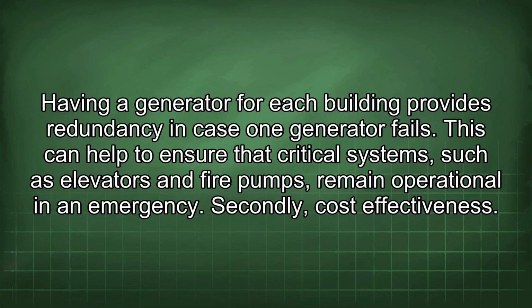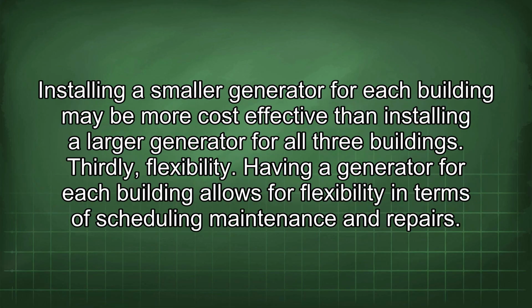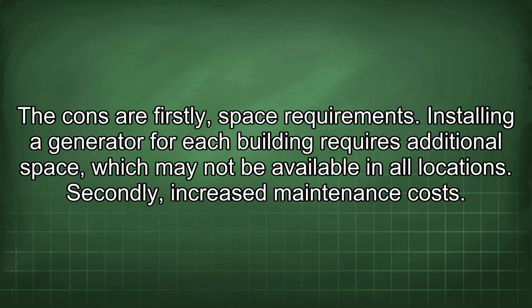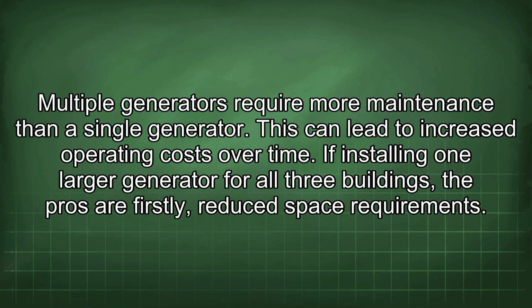Secondly, cost effectiveness. Installing a smaller generator for each building may be more cost effective than installing a larger generator for all 3 buildings. Thirdly, flexibility. Having a generator for each building allows for flexibility in terms of scheduling maintenance and repairs. The cons are, firstly, space requirements. Installing a generator for each building requires additional space which may not be available in all locations. Secondly, increased maintenance costs. Multiple generators require more maintenance than a single generator. This can lead to increased operating costs over time.